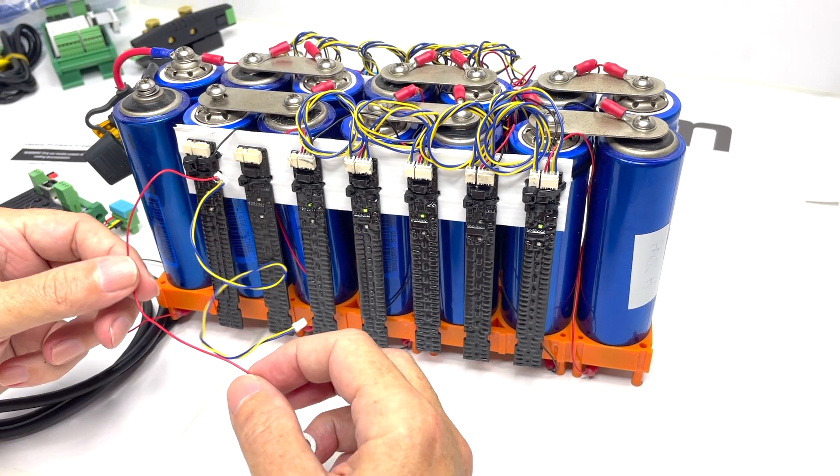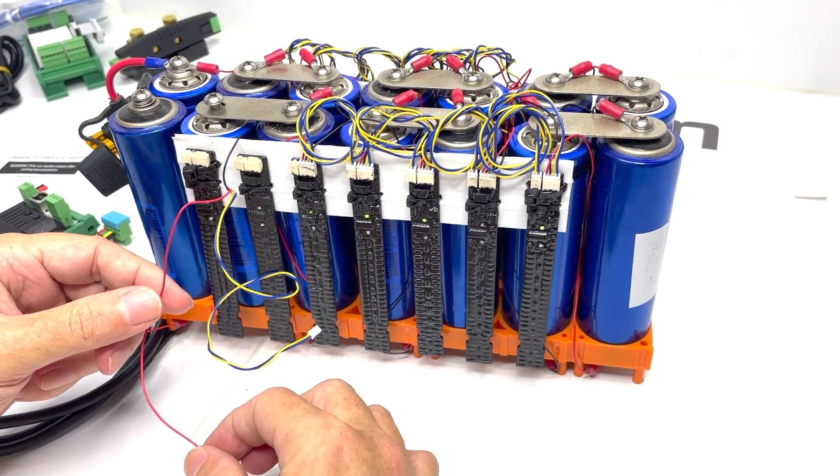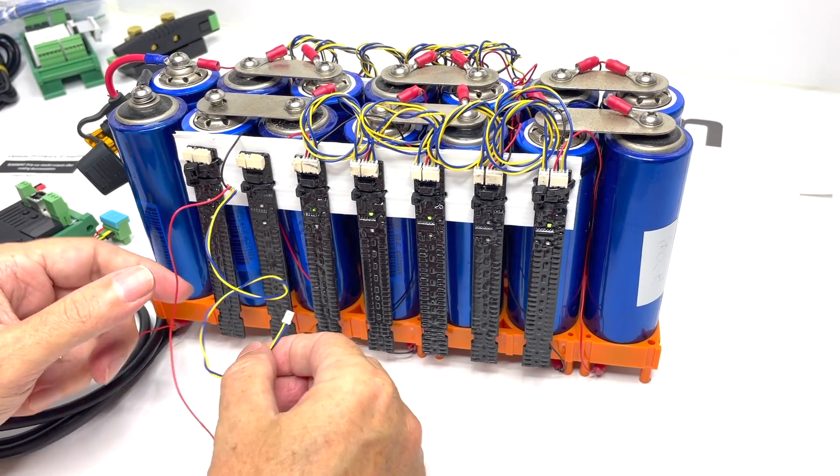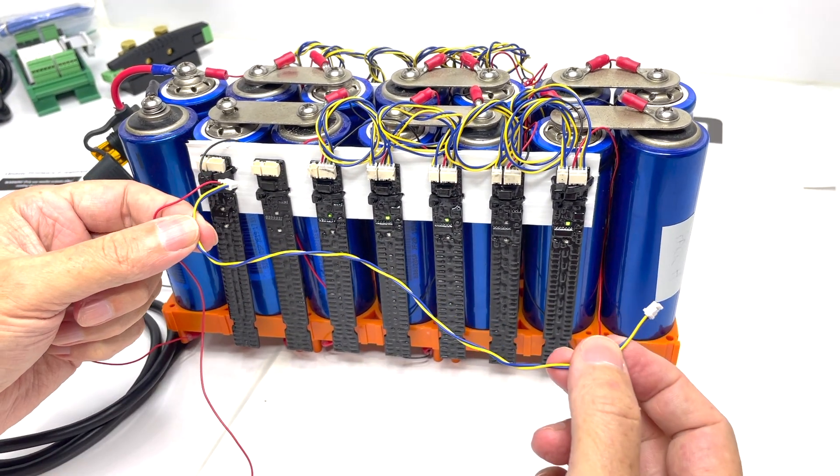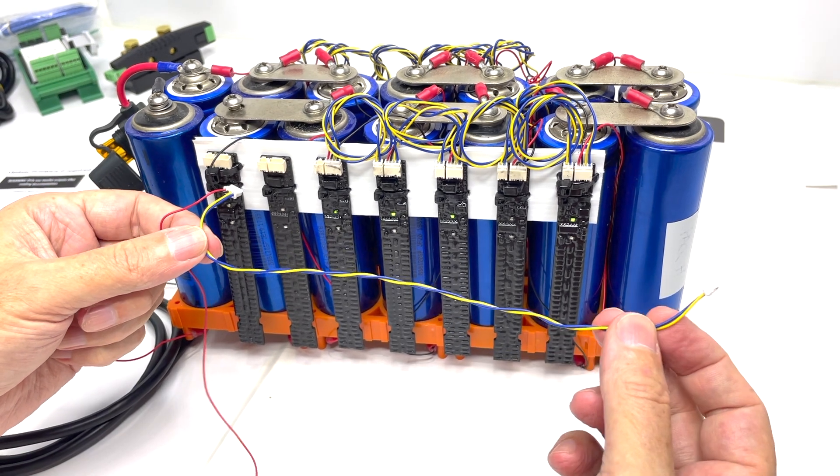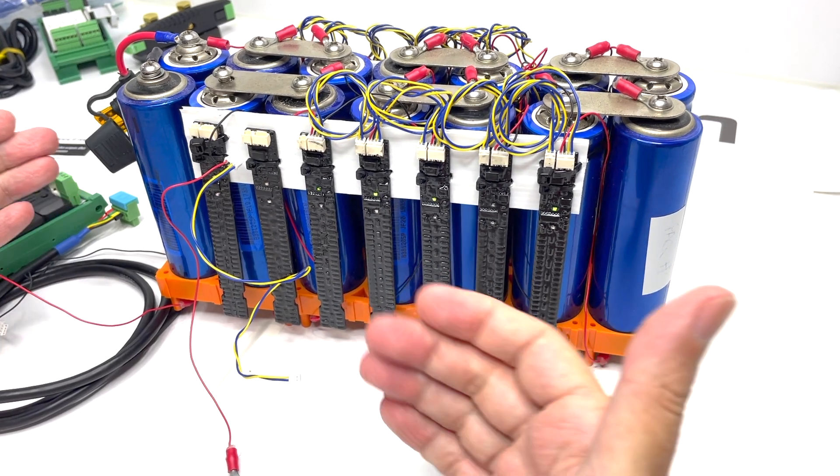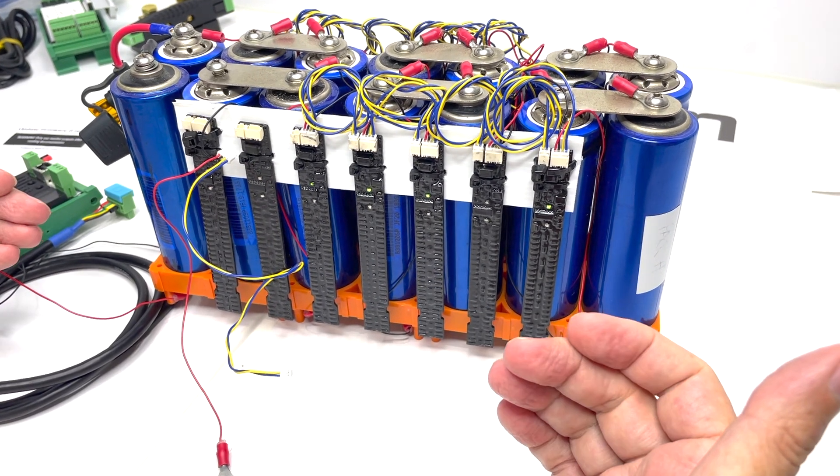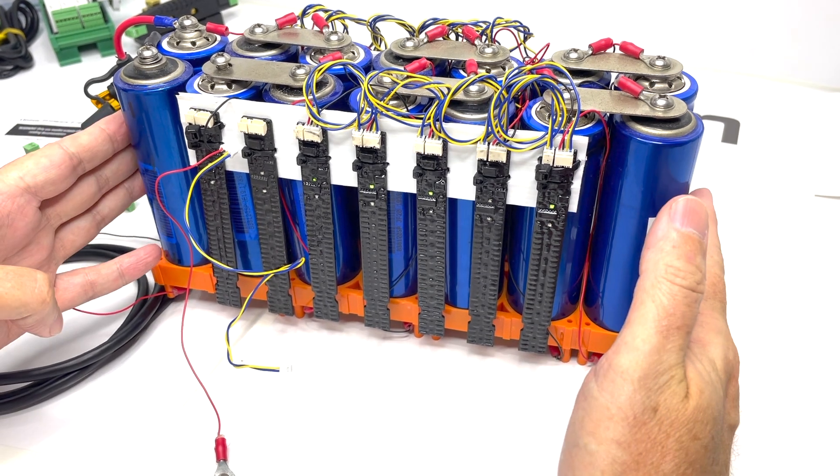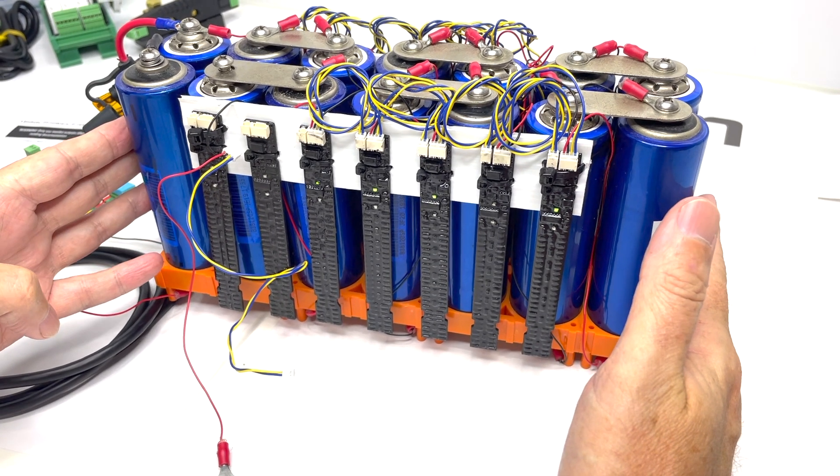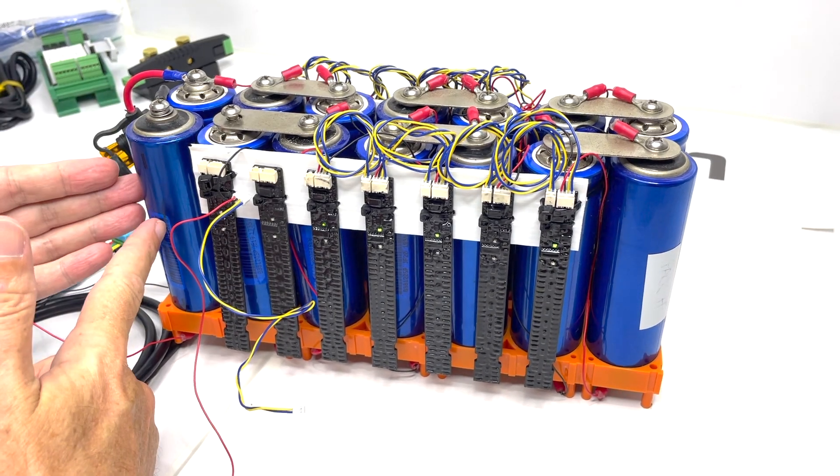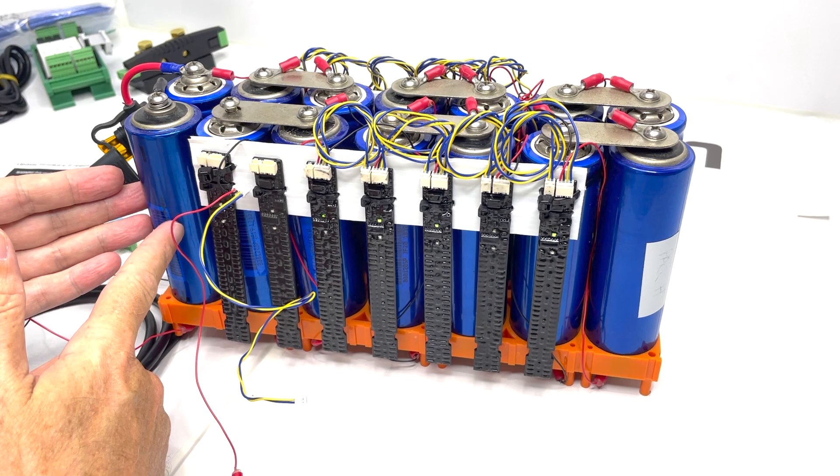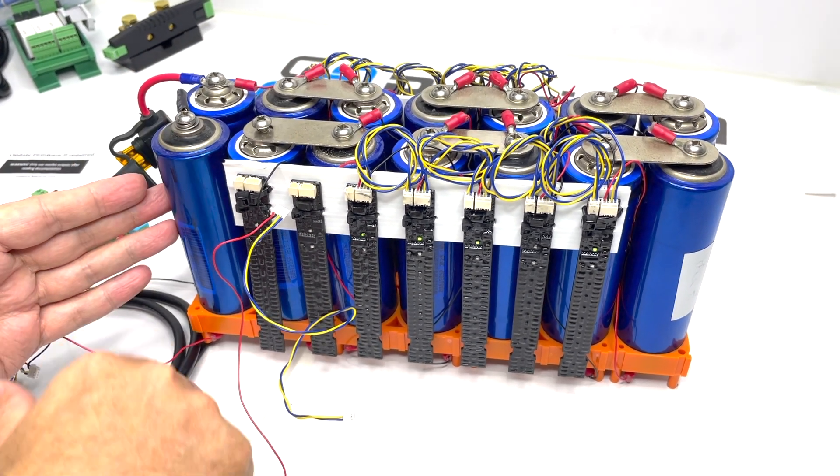Yes they can be extended but use the same size. Now for communication cable as long as you use twisted pair you can extend this up to five meters. Now the sequencing really matters with regards to the battery and the reason that it matters is for troubleshooting. We always recommend that you adopt the process of following the cell bus bar path.